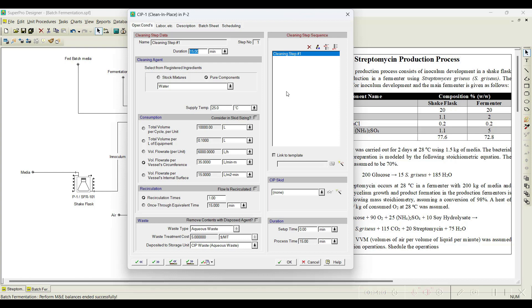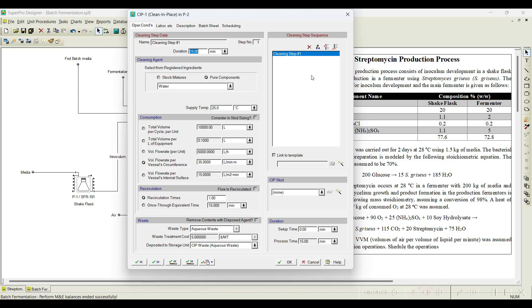For clean in place, the cleaning steps in a fermentation process are: first we clean with water, then we clean with maybe 0.1 normal or 1 normal NaOH, again we rinse with water, and again we clean with acid — for example 0.1 normal H2SO4. Once you clean with acid, again we rinse with water. So there is a series of steps in the cleaning procedure. You can add them here using the option to insert cleaning steps.